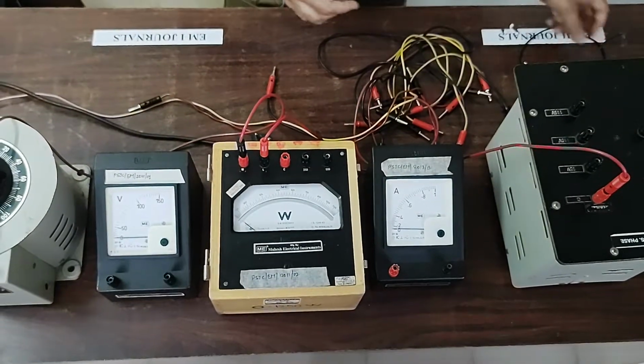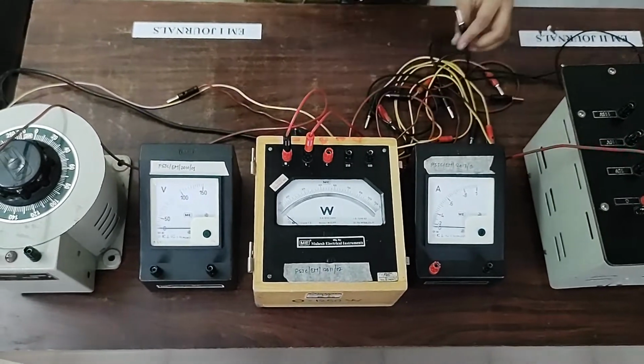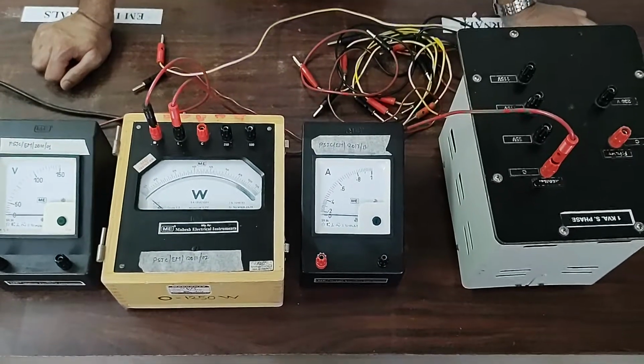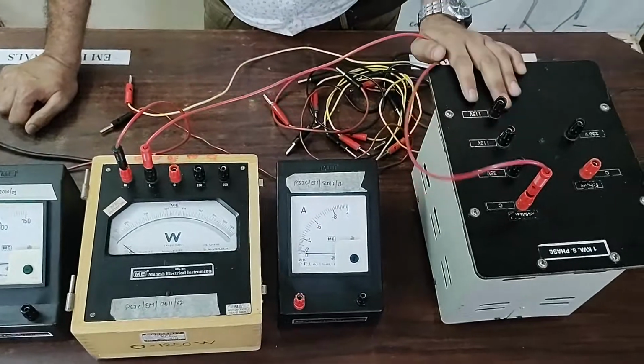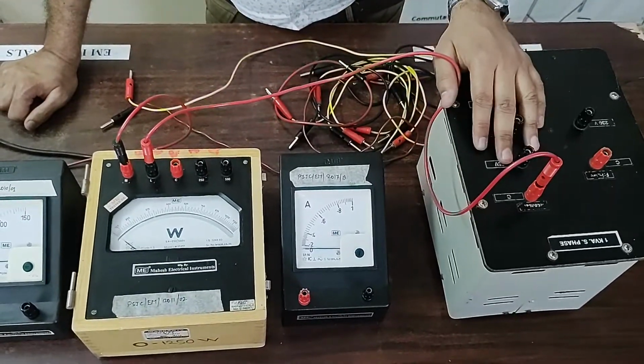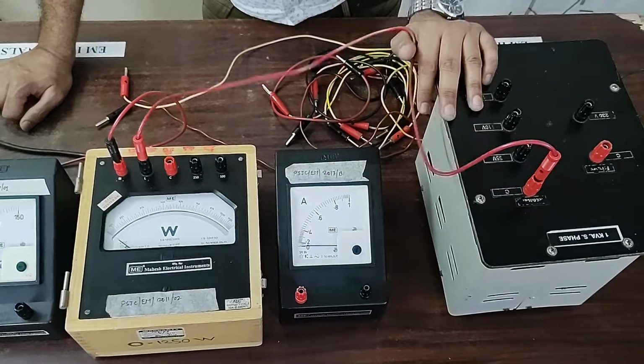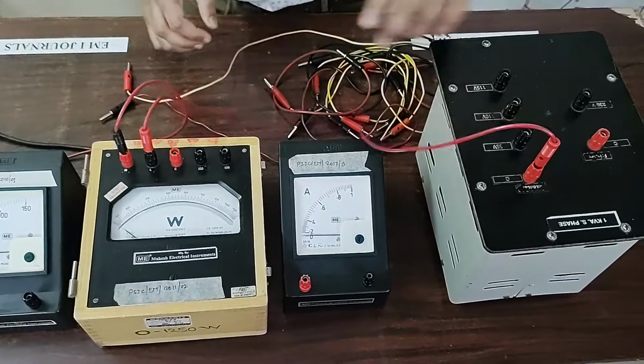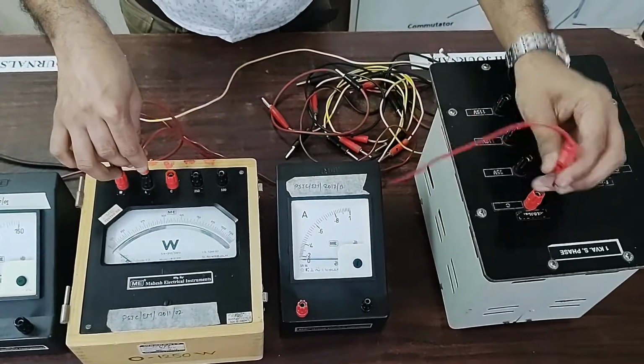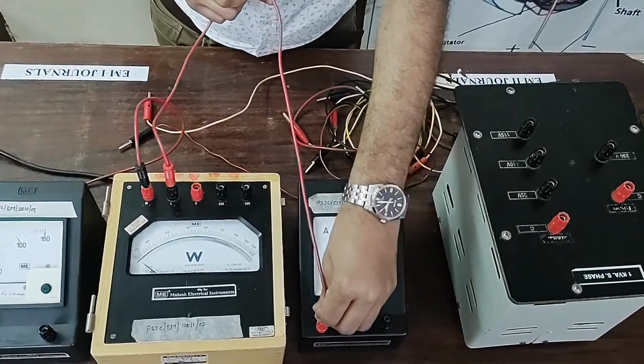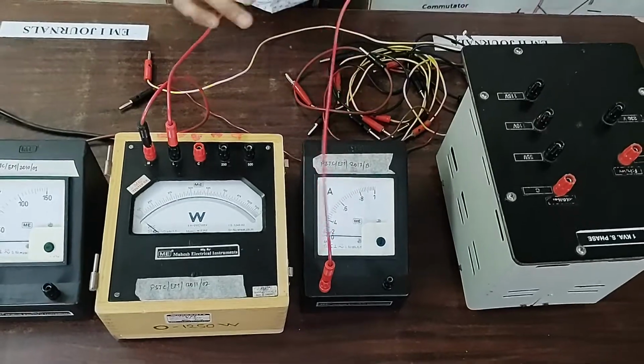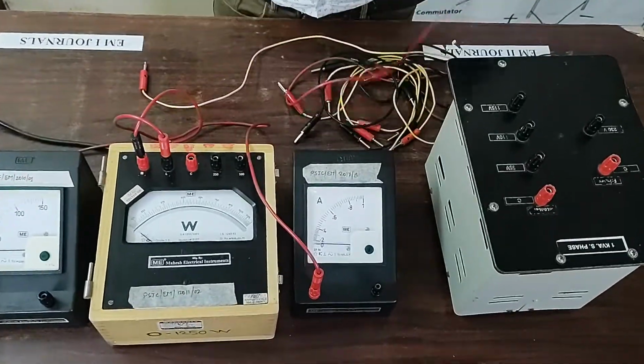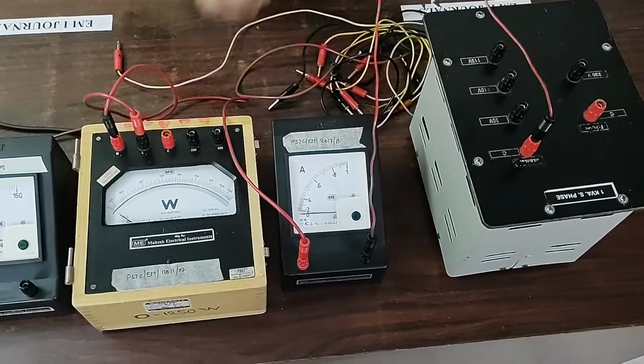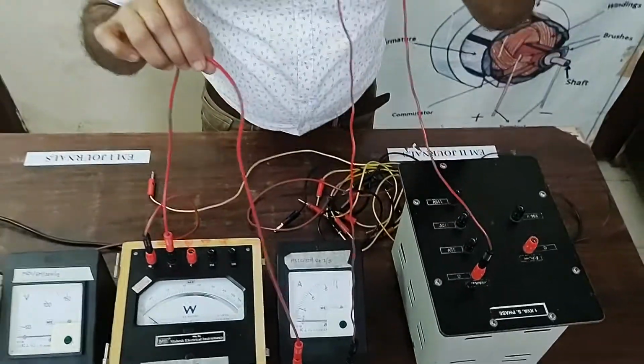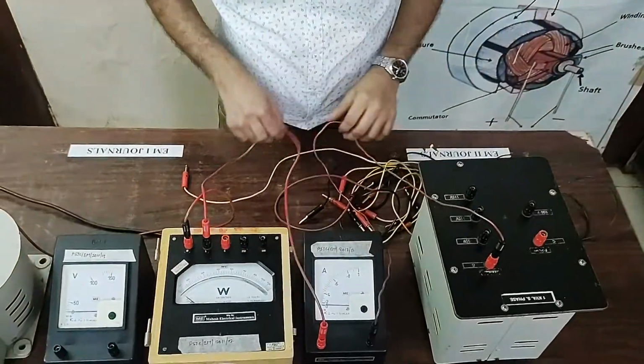Now, students, from the L terminal we have to connect it to the load, but here the load we are using is a transformer, and we also have to measure the current across the primary winding. So instead of directly connecting it to the transformer, from the L we will first of all make the connection to the ammeter. We will have to bring it in the circuit, not directly to the load, and from the ammeter we will take the connection towards the phase of the transformer. So this way we are bringing the ammeter in the series connection to measure the primary winding current.